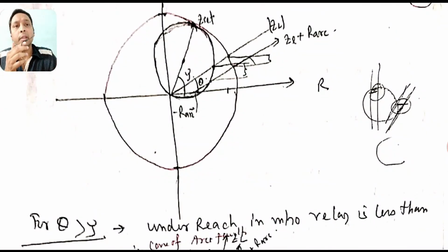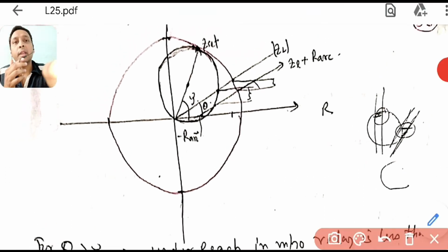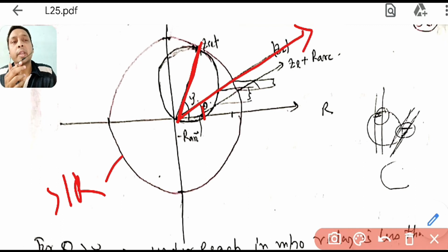Now you can see here, the bigger circle is for the SIR, simple impedance relay, and the smaller circle is for the Mho relay. You can see tau is more than theta because your ZL is here. So the condition was theta is less than tau. Now suppose an arc resistance has occurred, so the line has changed from here to here, because if you add resistance it will shift horizontally, since only the resistance part is added, as we have seen. Now see the underreach case.